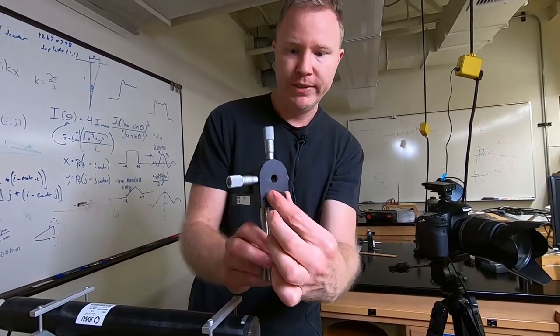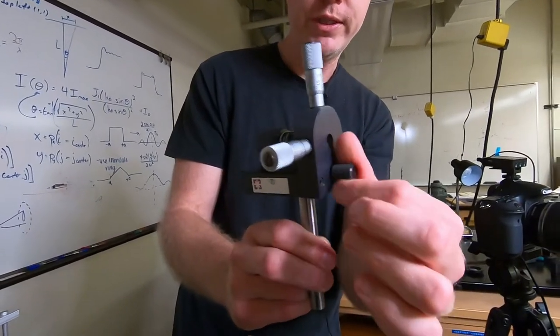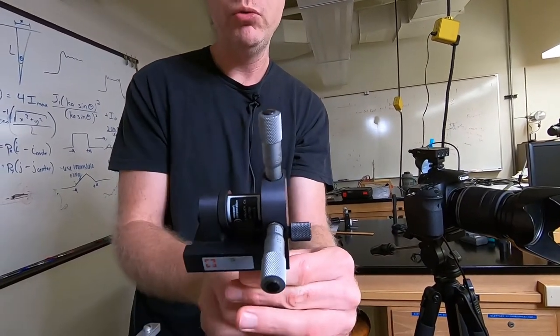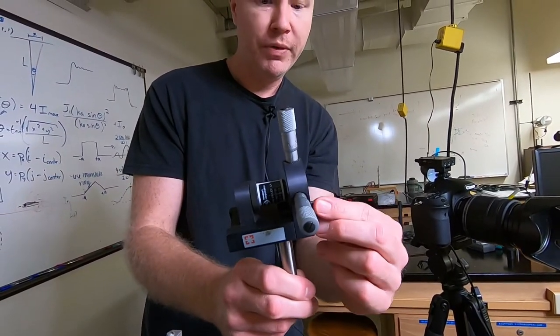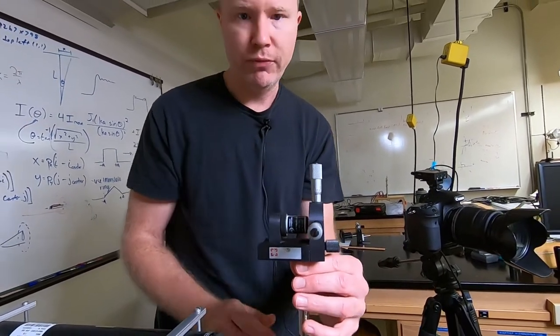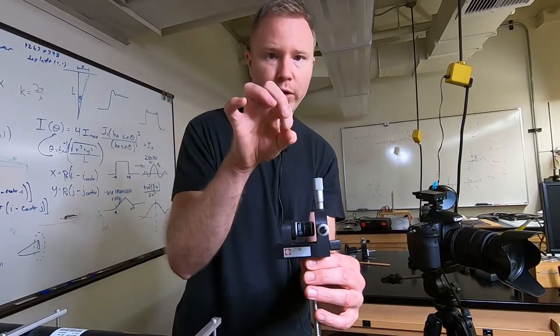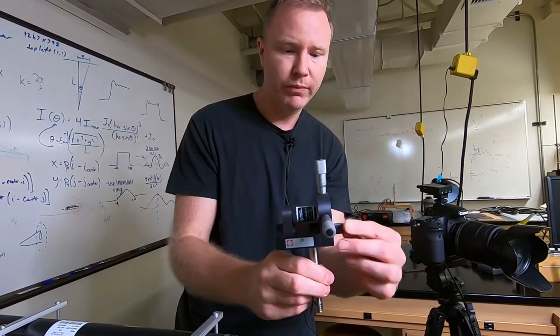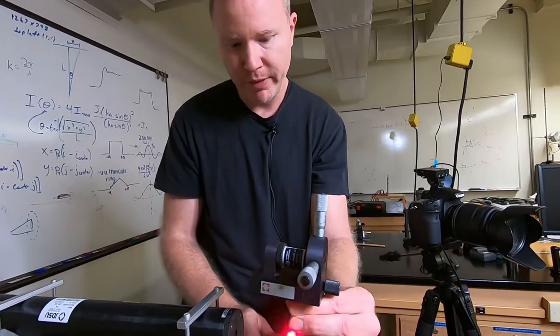There's a third knob here which is the Z direction. This just adjusts how close the microscope objective is to the pinhole. To start the process, I'm going to actually defocus it by quite a bit, because as the focus gets more and more correct, the X and Y alignment becomes more and more sensitive. So I'm setting it to a random focal position.